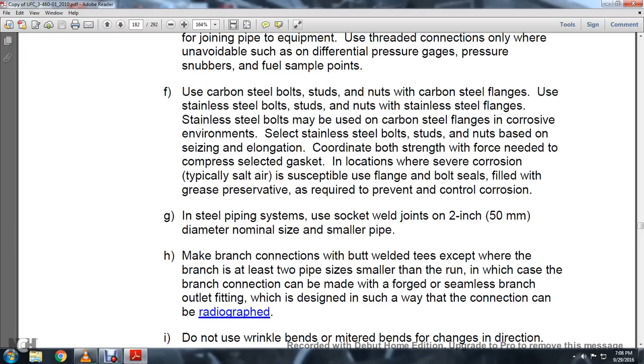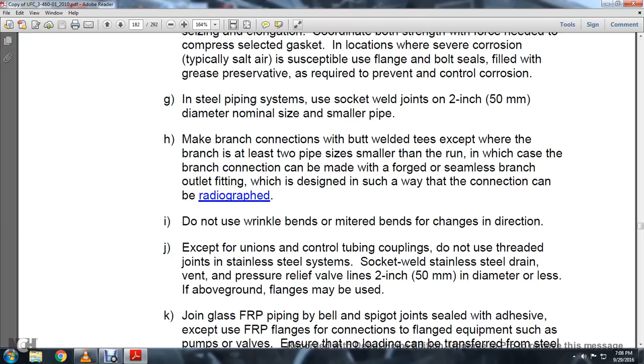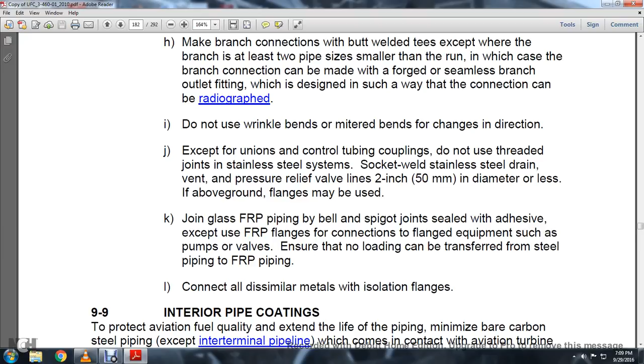Except for instrument control tubing and couplings, do not use threaded joints in stainless steel systems. Socket welded stainless steel drain, vent, or pressure relief valve lines 2 inches in diameter or less, if above ground, and flanges may be used. Join the glass FRP piping by bell and spigot joints sealed with adhesive, except for the FRP flange for connections to flanged equipment such as pumps and valves. Ensure that no loading can be transferred from the steel piping to the FRP piping. Connect all dissimilar metals with an isolation flange.